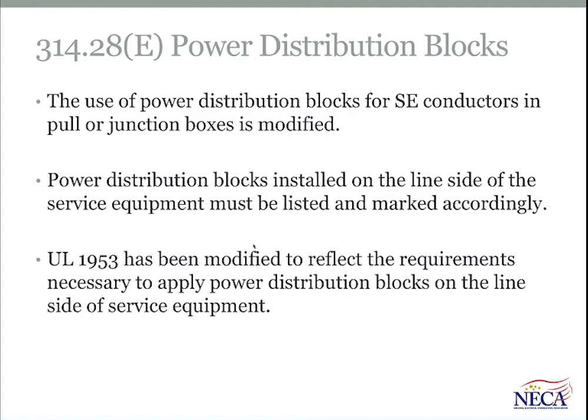Article 314 provides rules for junction boxes and pull boxes, and Section 314.28(E) has rules related to power distribution blocks. The change here recognizes that a power distribution block could be used on the line side of the service or the load side of the service. So with that understanding, power distribution blocks that are installed on the line side of the service equipment must be listed and marked for that specific use.